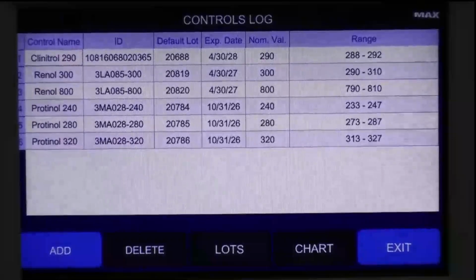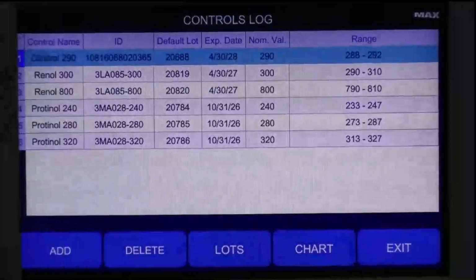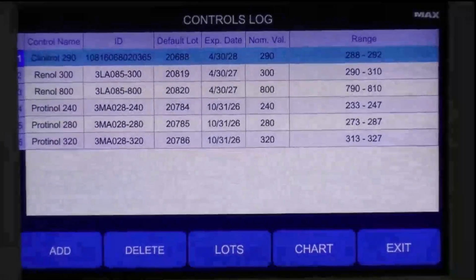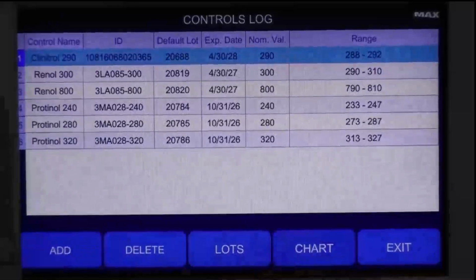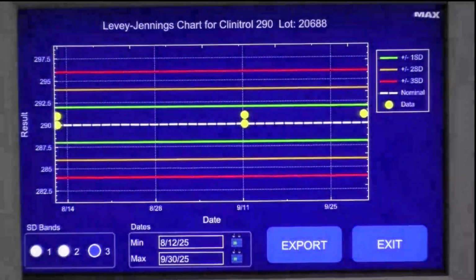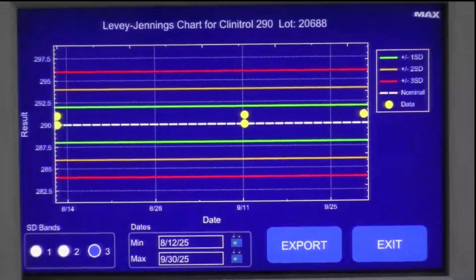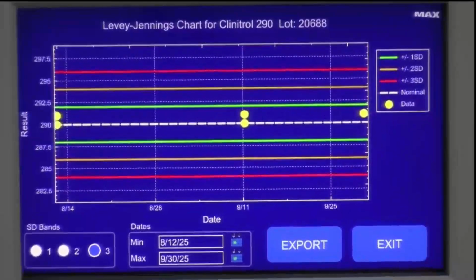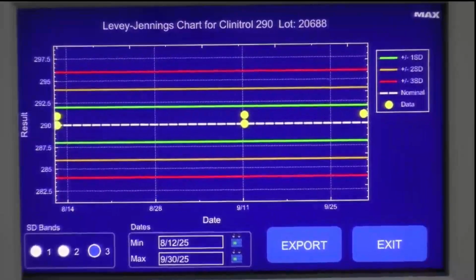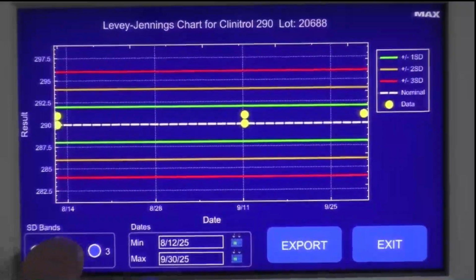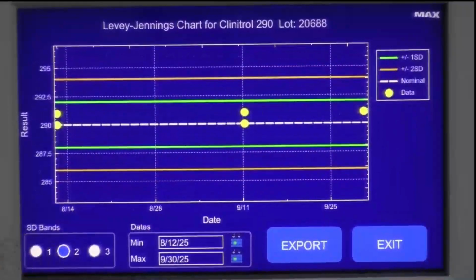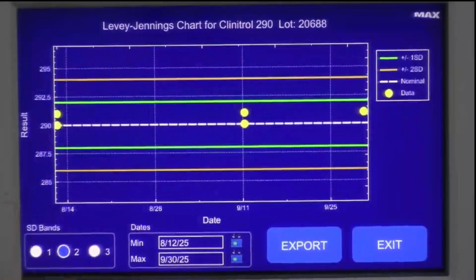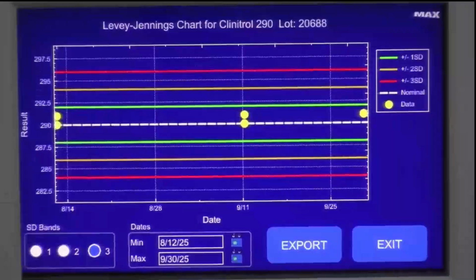So you can actually designate any given control at any time as your default lot. Not only that, but I could select this and hit chart, and then I can actually see how my controls have performed. So we can actually throw the Levey-Jennings plot right up from the inventory log, from the control log. You can filter by date if you want to. Those colorful bands that you're seeing on the top and bottom are standard deviation bands, so you can see how you're performing within a certain standard deviation if you'd like to. This instrument is performing really, really well. And you can actually limit the number of results you're seeing by a date range. You can also export that.